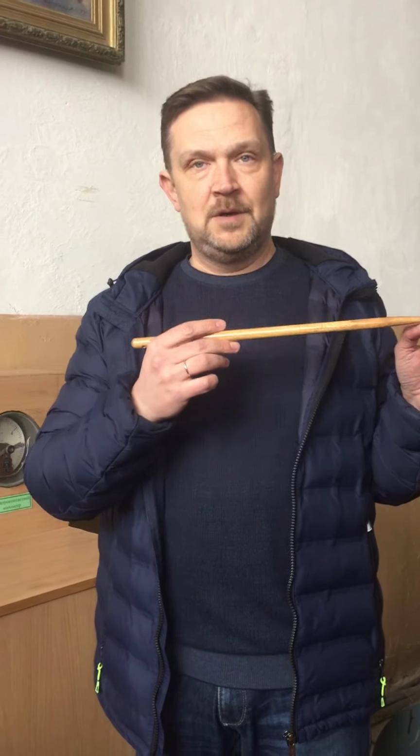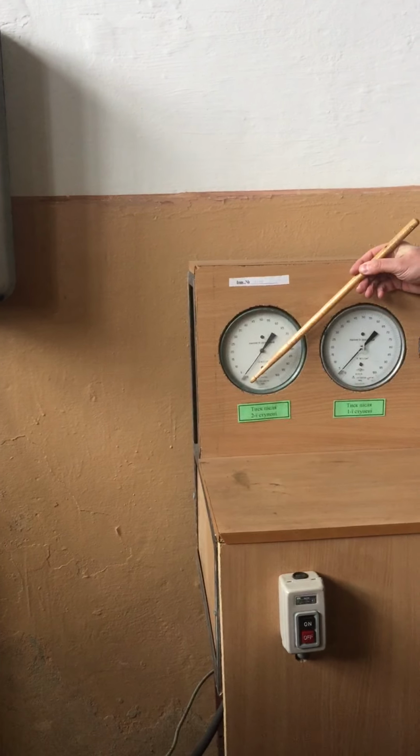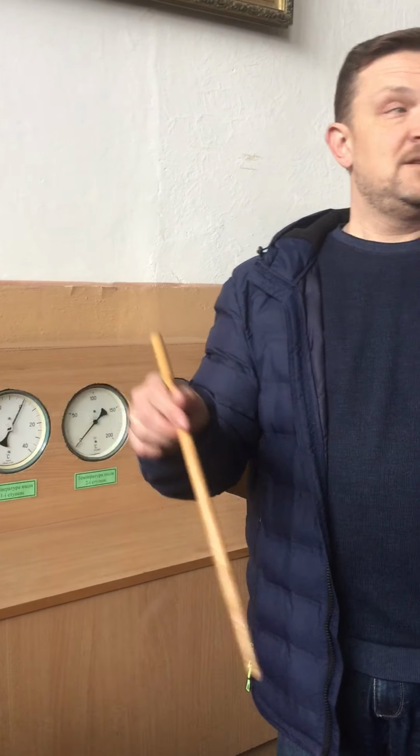We spoke a lot, when we spoke about the pumps, about the pulsation of the pressure because of the work of the pistons. Do you remember? We spoke of the dampener and so on. Here, on these two gauges, you will see the pulsation of the pressure in the air. The arrow doesn't go smoothly, because the pistons give the air portion by portion. The same process is in the piston pumps, so we have the same picture of the pulsation.